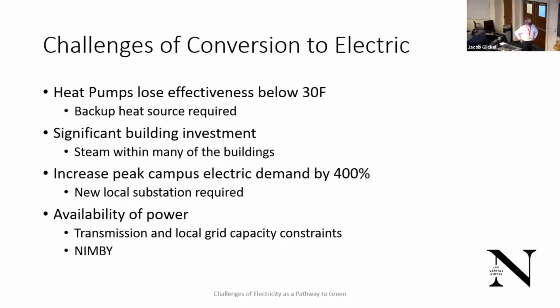We also found that an electric strategy would require increasing peak campus demand by 400%. We have 4 feeders to campus now; we'd need 4 times that many under the current configuration, or switch to a higher voltage from the substation. We'd need to site a substation, or convince the utility to site one in the neighborhood that could benefit Roxbury and the rest of the community, but siting a substation isn't a very popular thing these days, so that's a challenge.